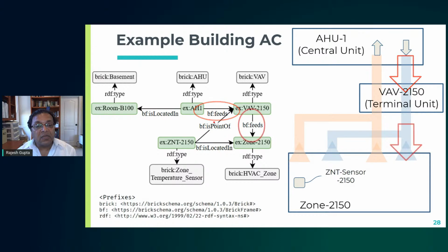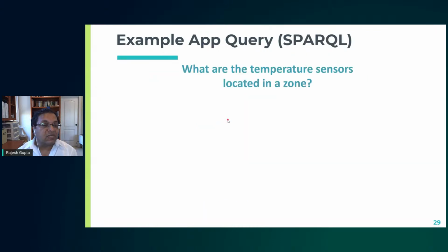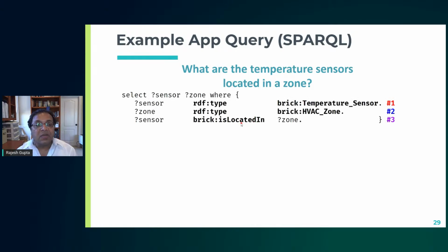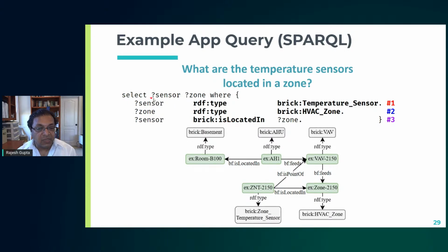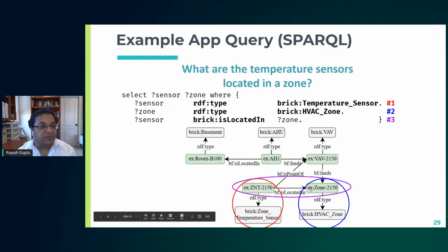So now, if you were to program and look for a question like, what are the temperature sensors located in a zone? This could be a simple query. So you could start to write triples. For example, you select the sensor, which is a query, and the zone, where these are the three query elements. So of RDF type sensor, in a given temperature sensor type. That returns to you this particular temperature sensor. What is the zone that it is located in? That returns the zone 2150. And therefore you have the connection between them, a location in, to make sure that these two points are connected together. This entire query matches this particular search. Okay.